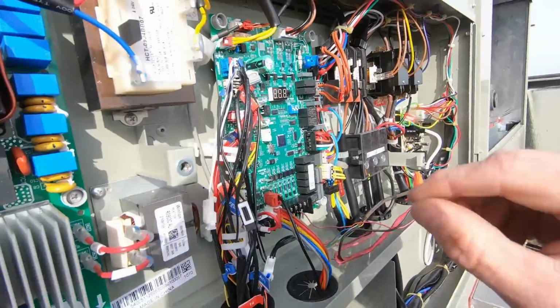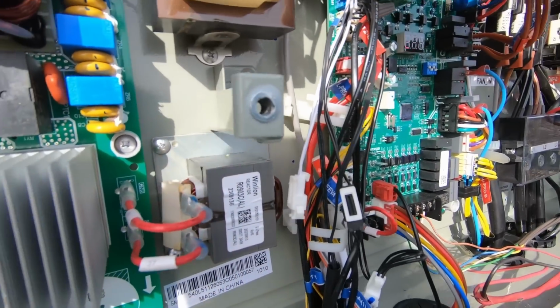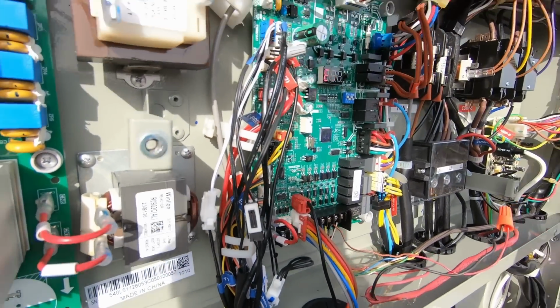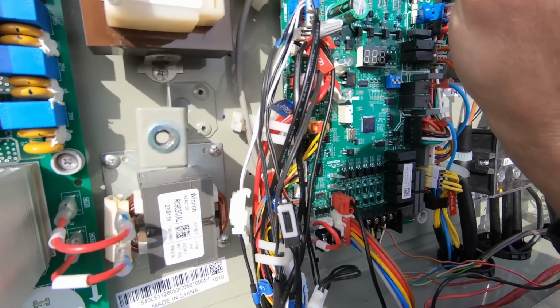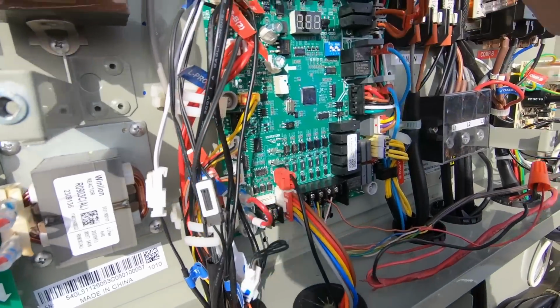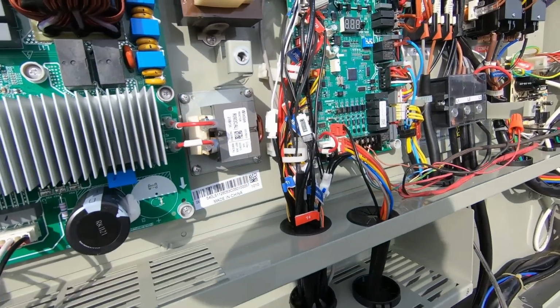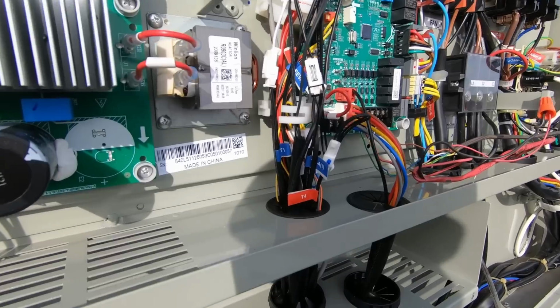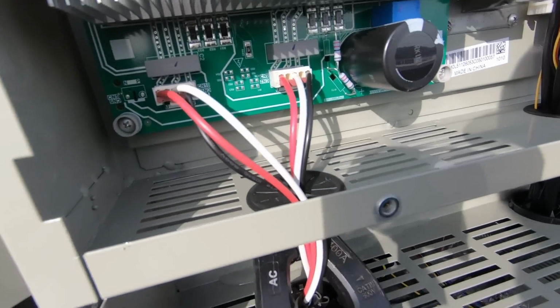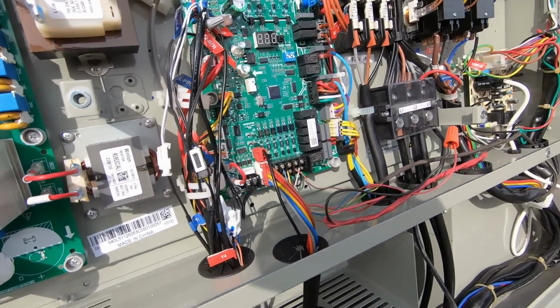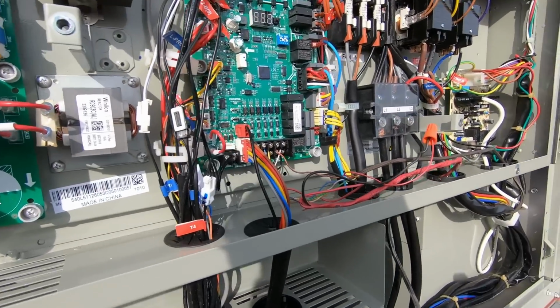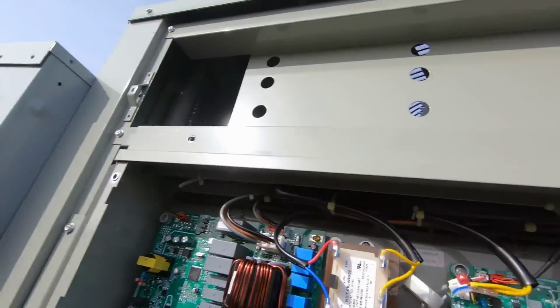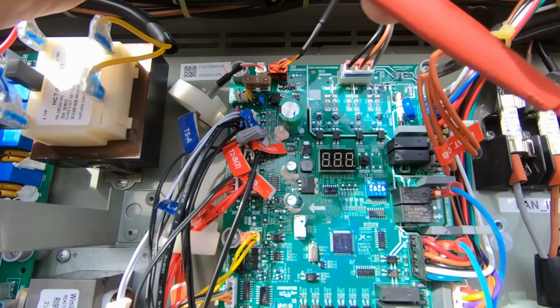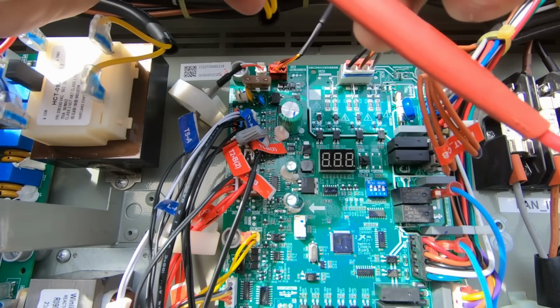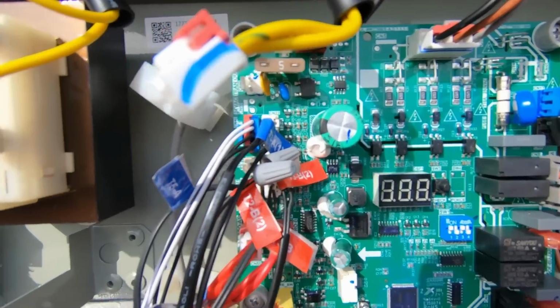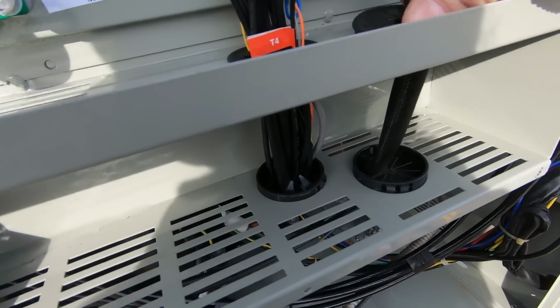Just gonna pull this and confirm that. If I can get this off, there it is. Yeah, so that's going straight from... oh, I just reset the board right there. So let's get my meter fired back up here as well. That sensor in the well took way too long, longer than I expected, just to put 2 zip ties on, but I had to bend my back out of place. And there we go, 24 volts. You can trust me on that. We have it. Oh my goodness.